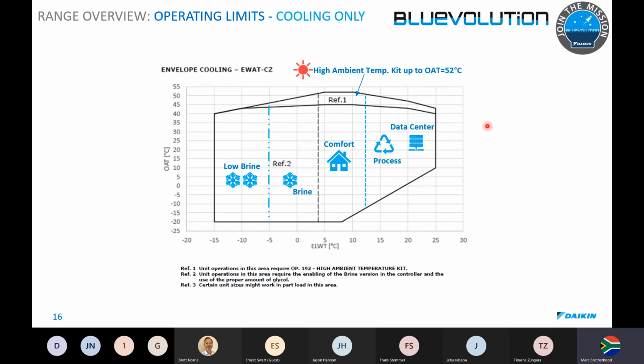And this is pretty much the parameters that these chillers fall into. Everything thermodynamically is balanced, so we do work within the confines of the thermodynamic laws and principles. So we can't take, sometimes, extreme high return water with a very high outdoor temperature and you wanting minus temperatures. We work within an envelope, which is what is thermodynamically possible. But we are able to calculate any of that for you on our software.